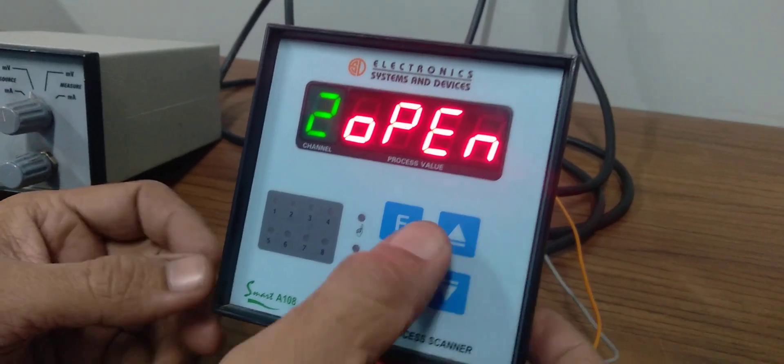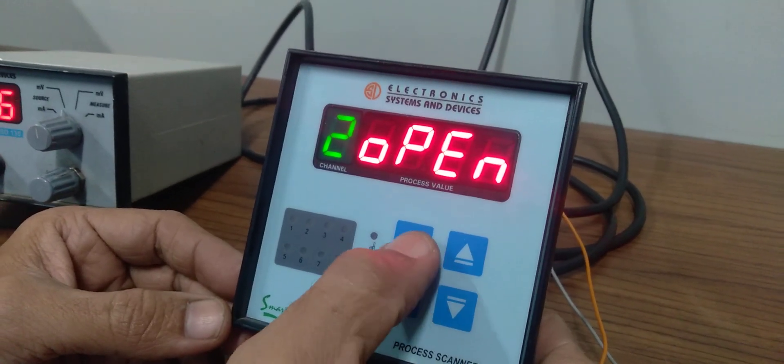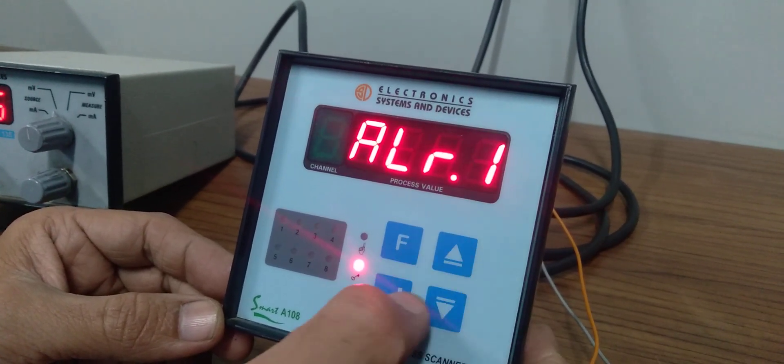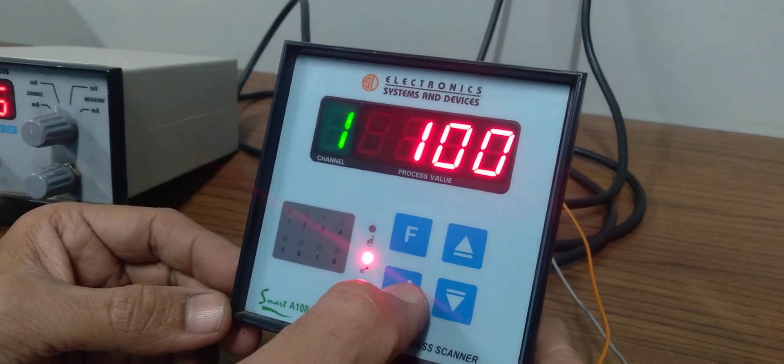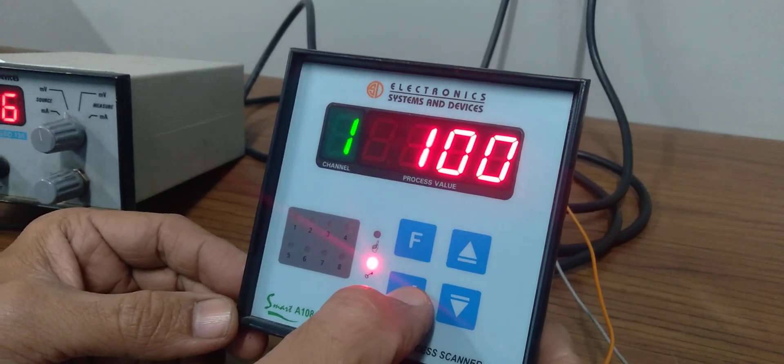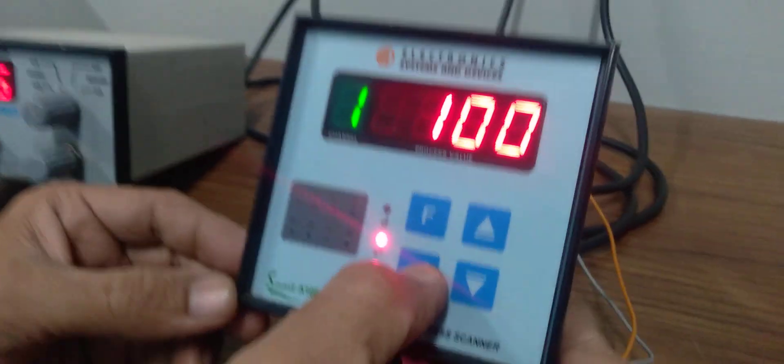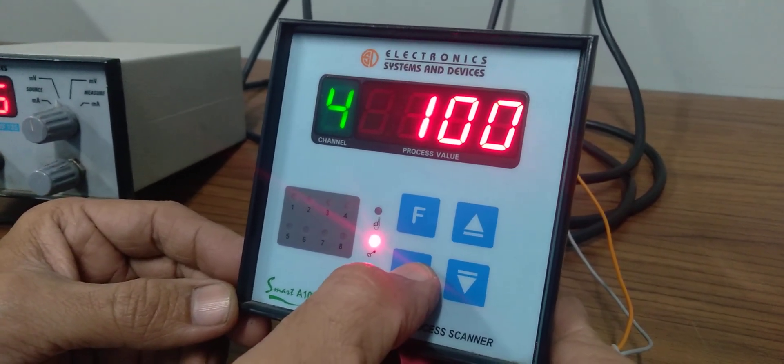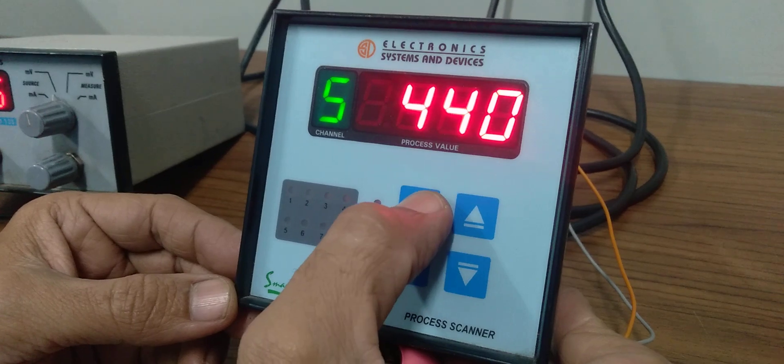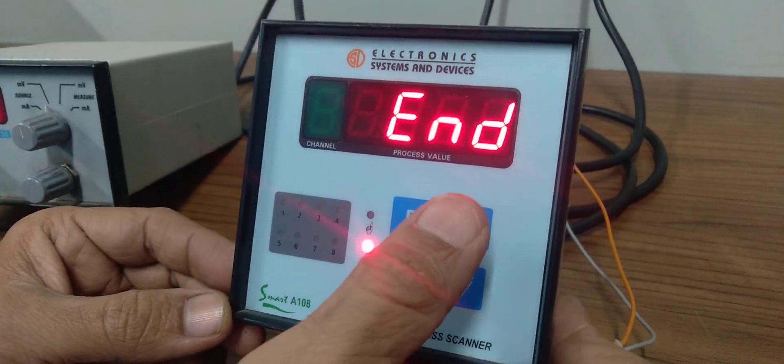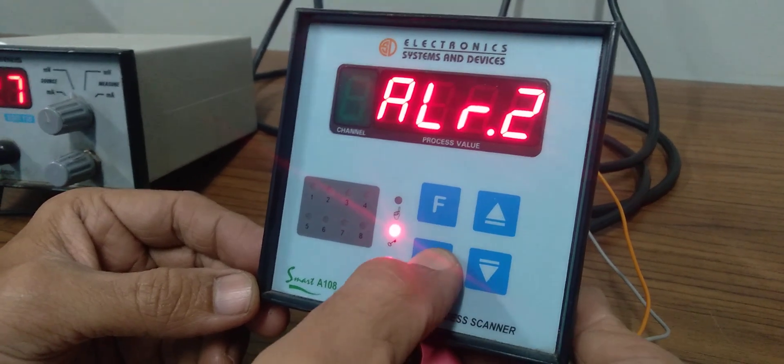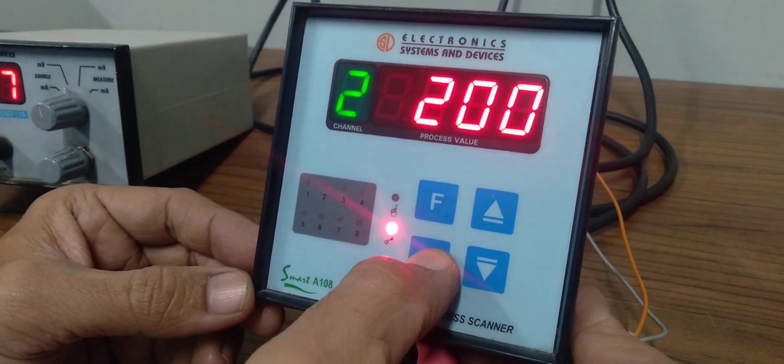Now we'll go to the alarm settings. Each channel has a setpoint. For alarm 1, we've kept it at 100 for channels one, two, three. All eight channels will have individual setpoints for alarm 1. Now we'll see alarm 2, which is for the trip setpoint. This one we've kept at 200. You can change any setpoint to whatever you want.